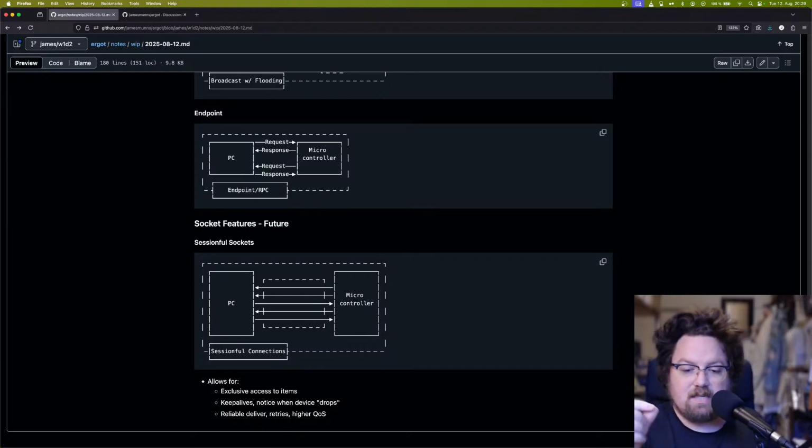And then the device has a chance to give back 0 or 1 packets. So if it just says, I have none for you, thank you, I'm done, it responds back immediately with none. And if it has 1 packet, it will give 1 packet. And if it doesn't respond, it puts a strike on that device, and after the device hasn't responded 3 times, it says, okay, that device is disconnected. And it throws away that device's address, and it just regularly polls all the devices on the network, and that way you don't have too much latency.